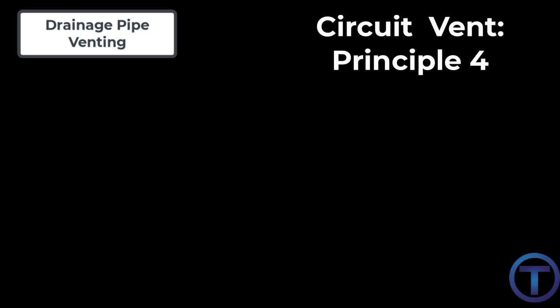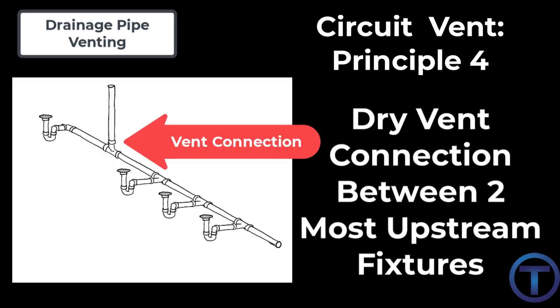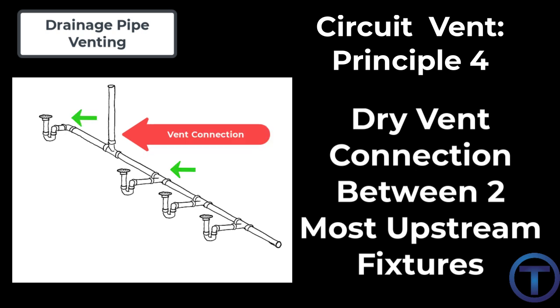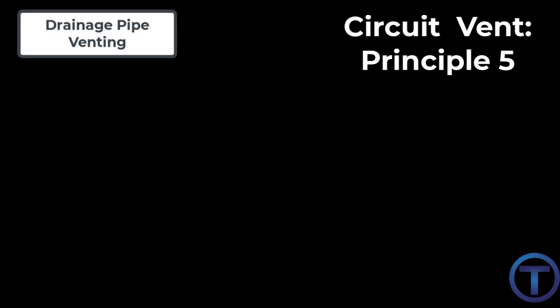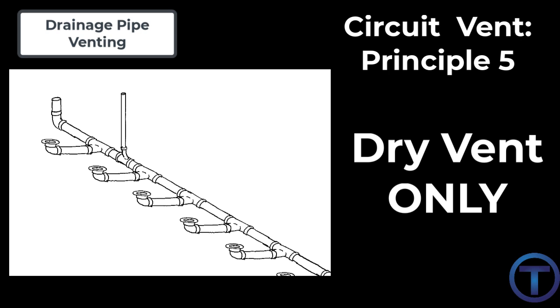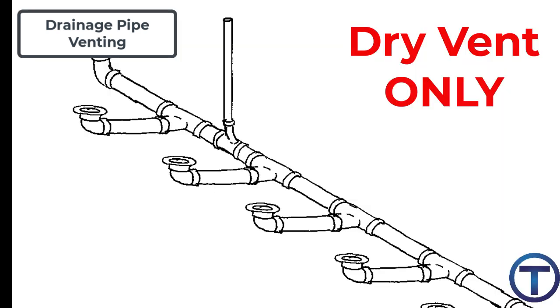Circuit vent principle four: the circuit vent connection to the dry vent must be between the two most upstream fixture drain connections. From there, it provides airflow downstream to all of the other horizontal drain connections in that circuit. Circuit vent principle five: the circuit vent pipe must be a dry vent and is not allowed to receive discharge from any fixtures. This is what really sets it apart from the wet vent, because the vent must be dry.